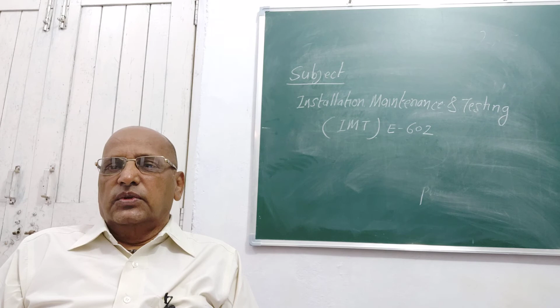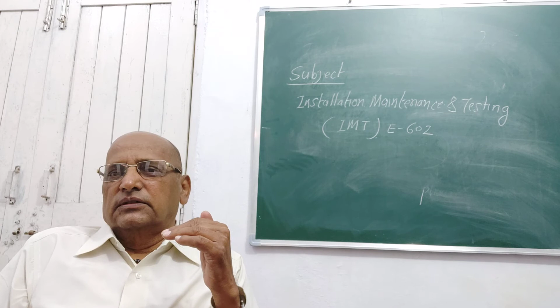So the LT distribution box is also heavy in nature because of the number of distribution circuits, MCBs, and bus bars in that box. It is to be installed on C channels, and we can use a single C channel, or you can also use angle iron for that. It is to be lifted again by the chain pulley block or proper ropes, so that it can be lifted up to a height of about 3.5 feet to 5 feet.